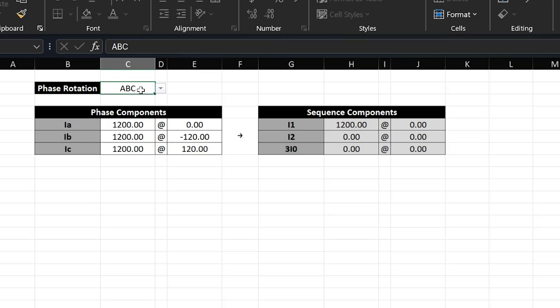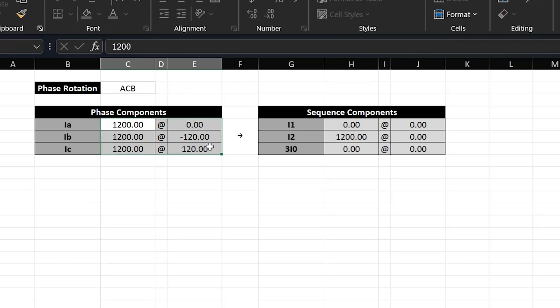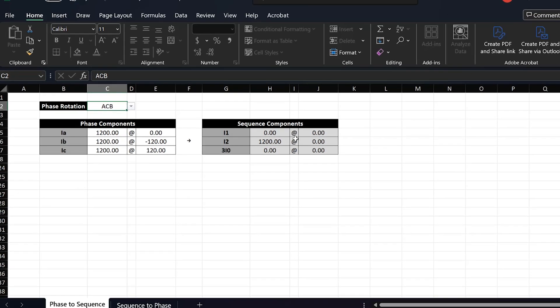To illustrate this, if I change the phase rotation for the system to ACB, you can see that now we get purely negative sequence current. The reason is that I've entered the currents with an ABC rotation but our system has an ACB rotation, so we get purely negative sequence current — and all of this is expected. The key point is that the symmetrical components calculation is affected by what we define our system phase rotation to be, which is set in cell C2.